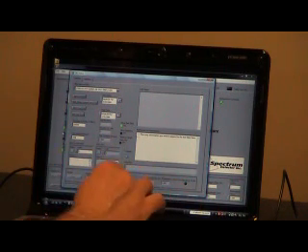The other way you can run this test, and I'll demonstrate that, let's see here. I'm going to set a test interval of about 6 seconds. I'm going to tell it to get 1,000 pulses in the batch, and I'm going to tell it to start right now because I want to do something right now. I'm going to go to lunch. I'm going to tell it to go out and get 5 tests. Now it'll come back and we'll say, where do you want to put those?